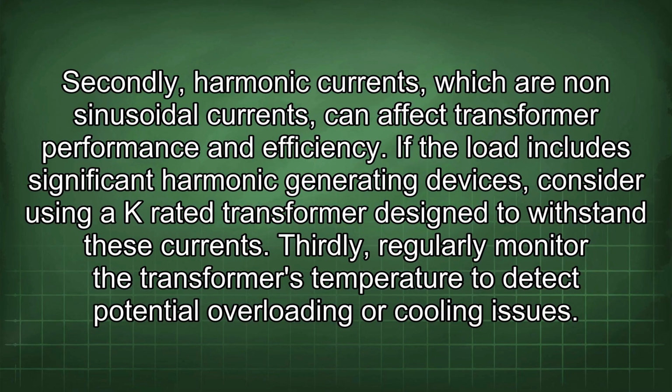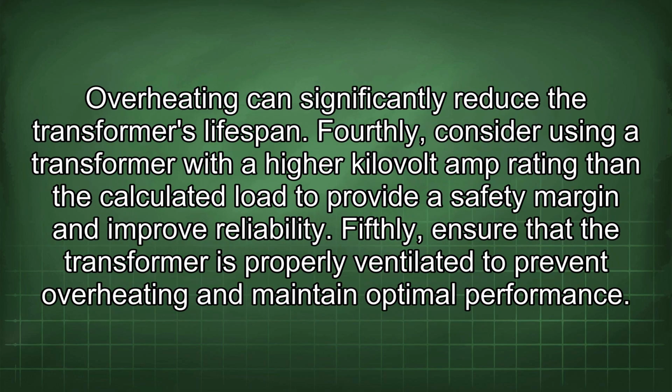Secondly, harmonic currents, which are non-sinusoidal currents, can affect transformer performance and efficiency. If the load includes significant harmonic generating devices, consider using a K-rated transformer designed to withstand these currents. Thirdly, regularly monitor the transformer's temperature to detect potential overloading or cooling issues. Overheating can significantly reduce the transformer's lifespan. Fourthly, consider using a transformer with a higher kilovolt amp rating than the calculated load to provide a safety margin and improve reliability. Fifthly, ensure that the transformer is properly ventilated to prevent overheating and maintain optimal performance.